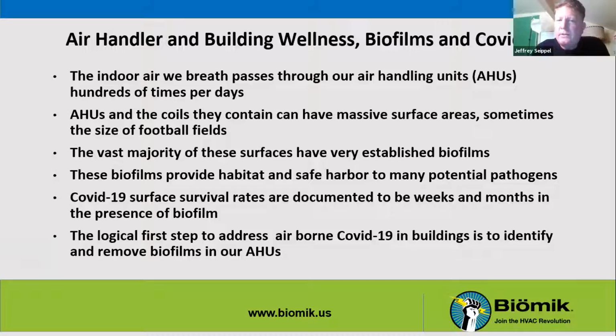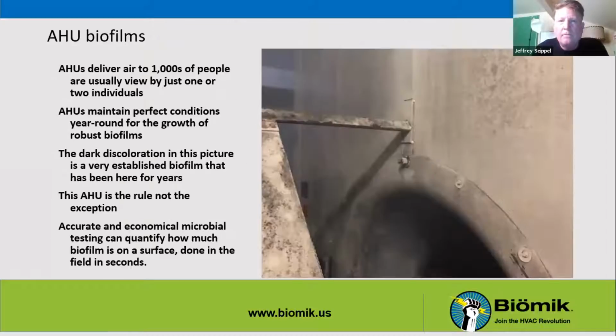So the logical first step to address an airborne COVID in a building is to check the air handlers and see what kind of situation you're in and how much biology you actually have in the air handler. Air handlers are not seen by most people in a building. There's usually only one or two techs that actually stick their heads in them. They maintain very good conditions for biological growth year round. You see the dark discoloration on this blower here, and that is an established biofilm. This air handler is not an exception. It's more of the rule of what I see on a day-to-day basis.